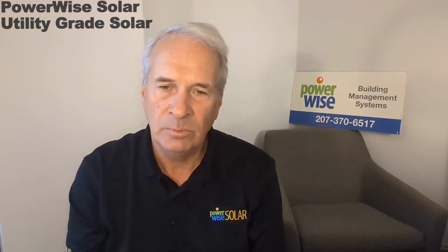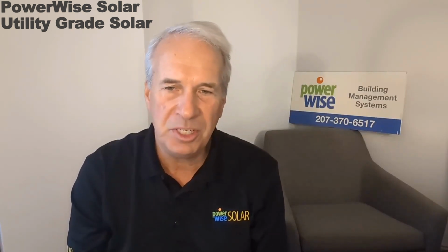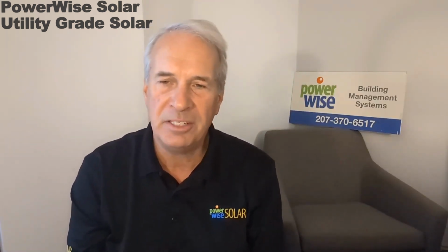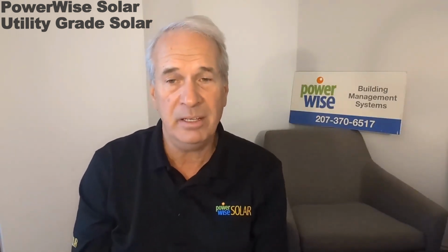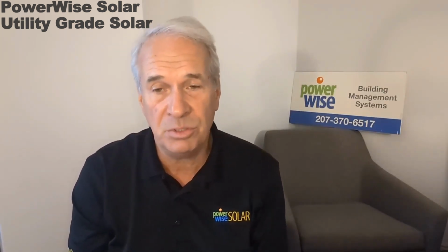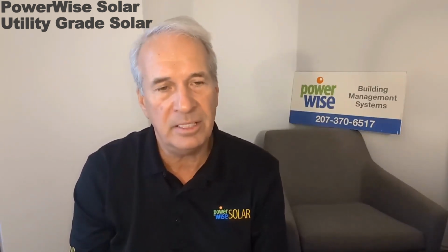Now, typically in a utility installation, about how many weather stations do you usually have on site? Normally we say it's always at least two met stations, so you have some redundancy and also the variation across the site. It's two met stations up to 20 megawatts, and then one additional met station for every 20 megawatts after that. For example, we're bidding on a very big site in Texas, which is 372 megawatts. That's huge, which means such a plant would need around 10 high-end met stations.